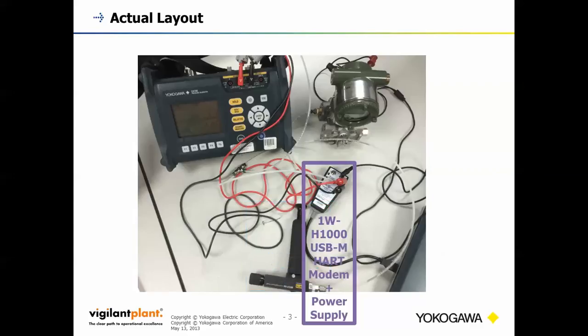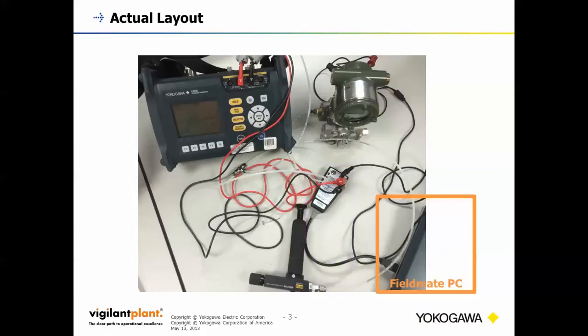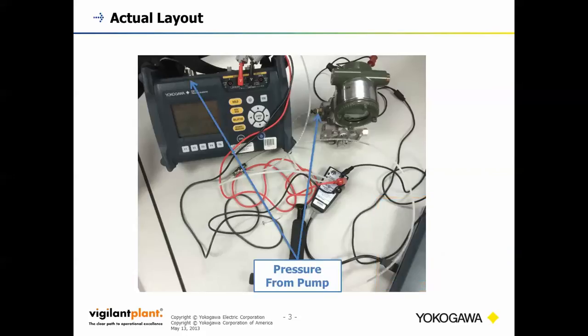We've got our HART modem and power supply that is providing communication from our transmitter to our PC via HART and also powering the transmitter. Then we have our Fieldmate PC, which will help us facilitate our calibration and also provide us with configuration for our transmitter. These blue arrows are just highlighting how the pressure is going from the pump to the transmitter and the calibrator, so they're connected both with the blue arrows.